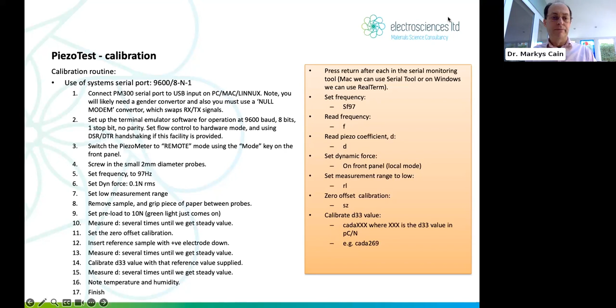Anyway, so once you set up the serial port, you switch the piezometer to remote mode, and you can start doing some measurements. And then, of course, every time you press D, return, you can read in the D coefficient. Okay, and that's fine. You can also then put a reference sample in, and you can measure D several times, and that will then be theoretically your calibrated value, which you then write back to the unit, because you're using quartz, for example, or lithium niobate, for example. So this is the sort of thing that you would have to get used to doing if you have a machine like this and you want to seriously make sure that it's calibrated and you know how to calibrate it. You need to be able to use a serial port simulation, and do these sorts of things. And it's not too difficult, but it just takes a bit of time to get it set up.